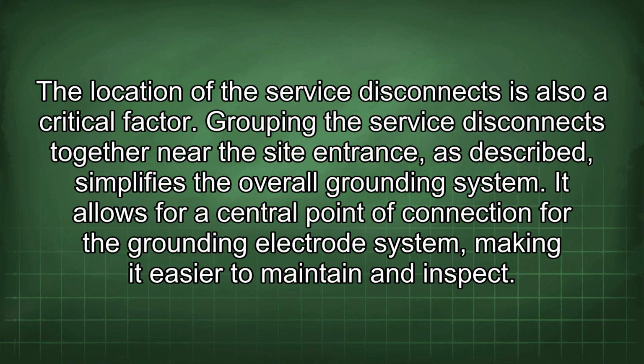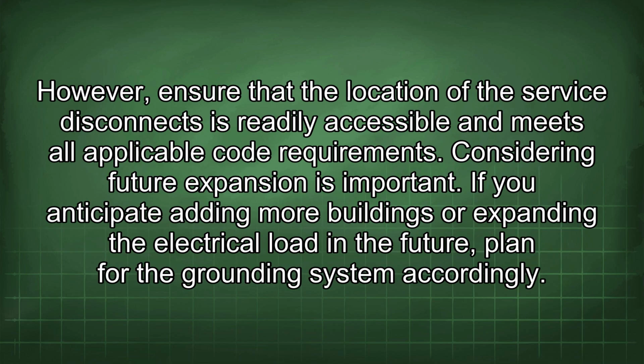The location of the service disconnects is also a critical factor. Grouping the service disconnects together near the site entrance, as described, simplifies the overall grounding system. It allows for a central point of connection for the grounding electrode system, making it easier to maintain and inspect. However, ensure that the location of the service disconnects is readily accessible and meets all applicable code requirements.